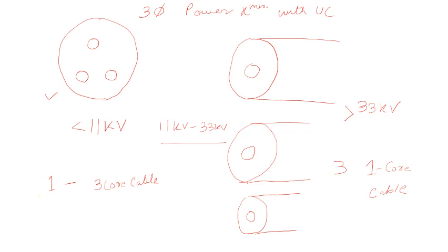So let's start. Basically, we will be more focused on the three core cable, and we will be checking the capacitance per phase across this cable. Then we will decide the parameters, that is your charging current, and then the reactive compensation in your three core cable.